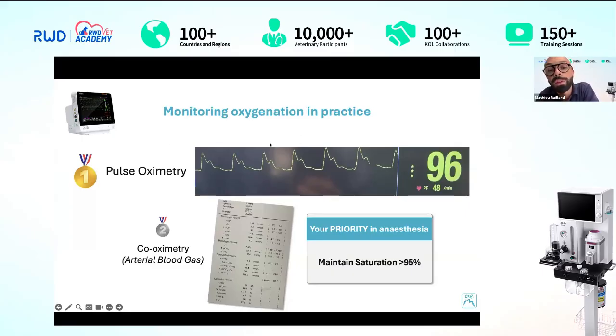So before reading the saturation value, which is the one we are interested in, we need to ensure that the monitor is actually looking at the right portion of the tissue. Saturation is the percentage of hemoglobin that is saturated. We are interested in the saturation of the hemoglobin in the arterial bed, and therefore we're interested in the pulsatility. So we need to see that the monitor is looking at the right thing. We need to see a good pulse curve to know if we can trust the saturation value displayed by the monitor.